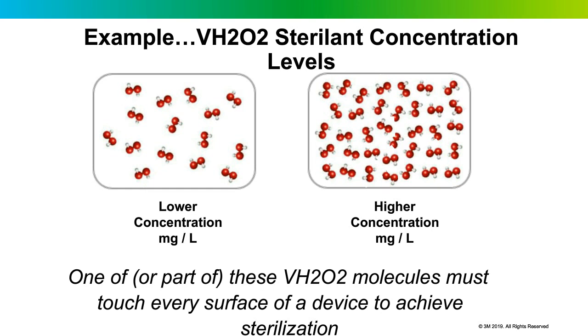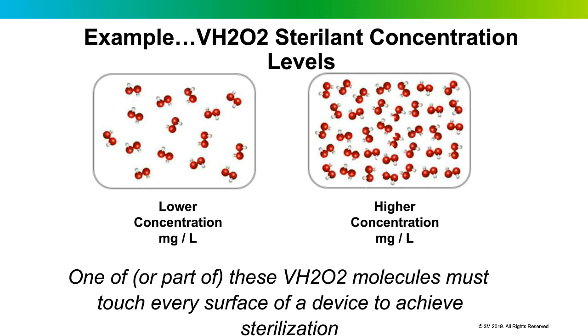All sterilizers in U.S. healthcare facilities operate at different concentrations, using different amounts of hydrogen peroxide to achieve sterilization. The Sterrad 100S has one of the lowest concentrations at around 6–7 mg/L. The Steris V-Pros operate at a slightly higher concentration of around 9–10 mg/L. The ASP Sterrad NX versions use an estimated 25–28 mg/L — significantly more than the Sterrad 100S, even though they come from the same company.